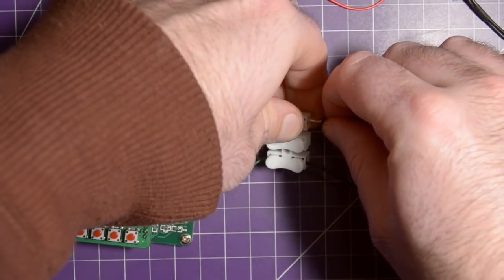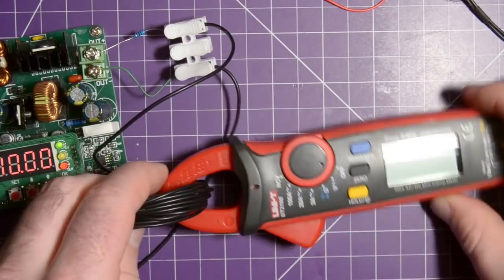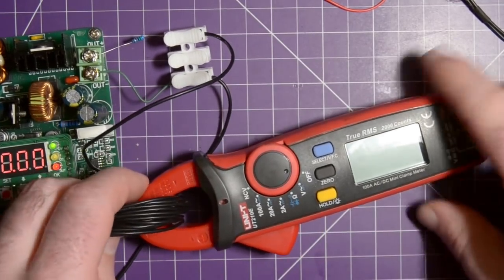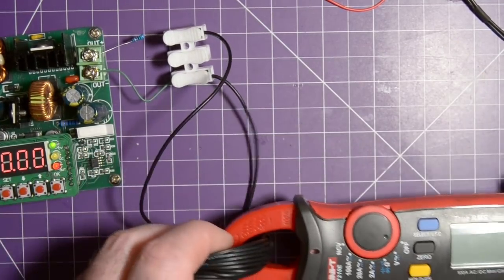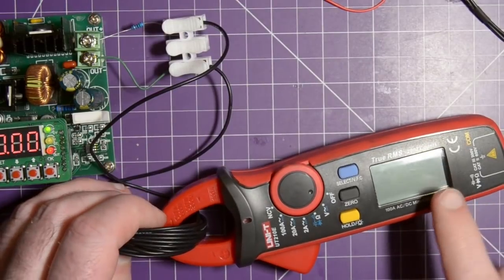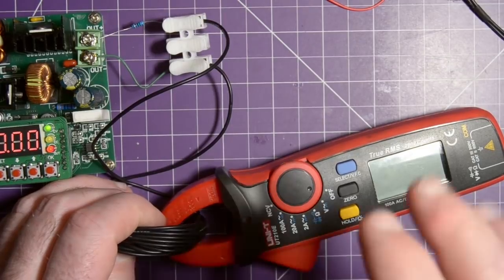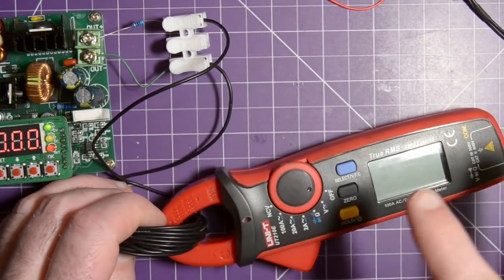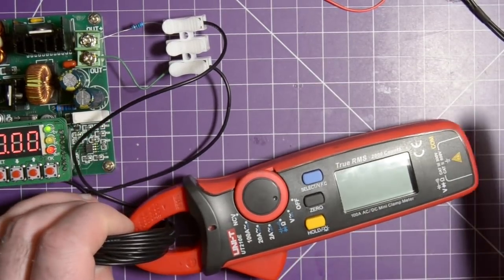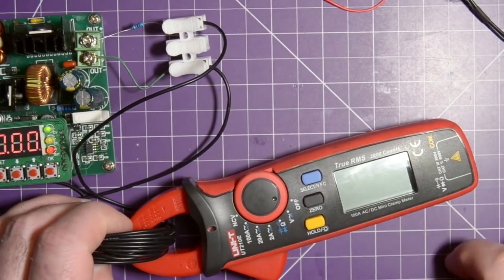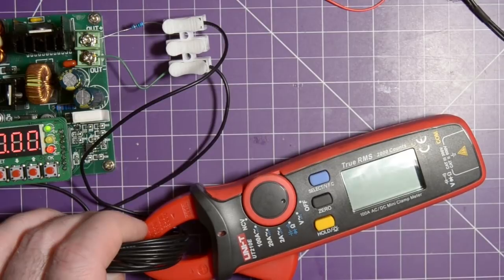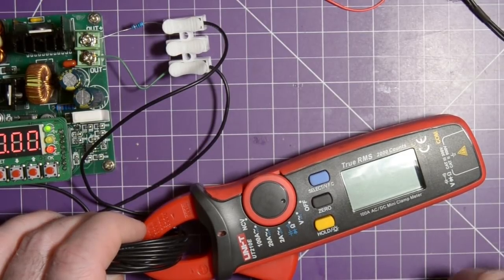So now we should be able to get a reading on this clamp meter. We should be able to get a reading that'll be twenty times higher than what the actual amperage is. So in this case we should see about 26-27 milliamps, which is 0.001333 repeating times twenty.